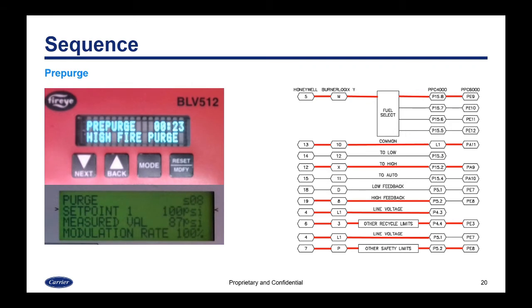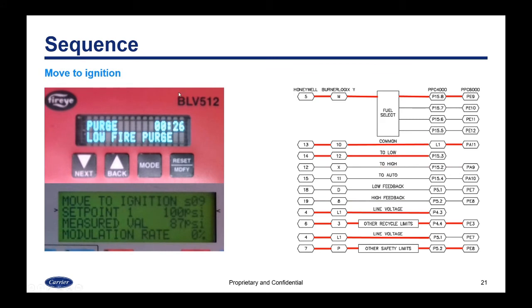Once the limit is proven, the voltages are all the same here, but now we have high feedback coming back to the flame safeguard. So we still have the signal to go to high, but now we have high feedback as well. The PPC is going to display purge. The flame safeguard is going to begin its purge and count down. When the purge is complete, we're going to want to move to ignition.